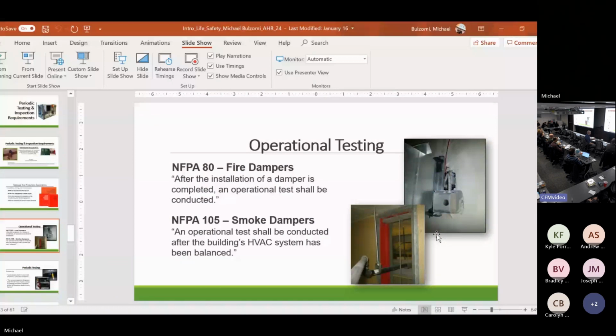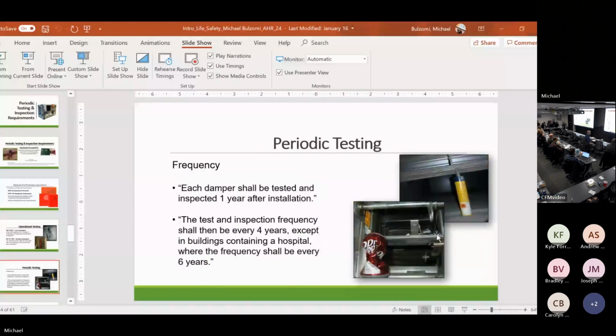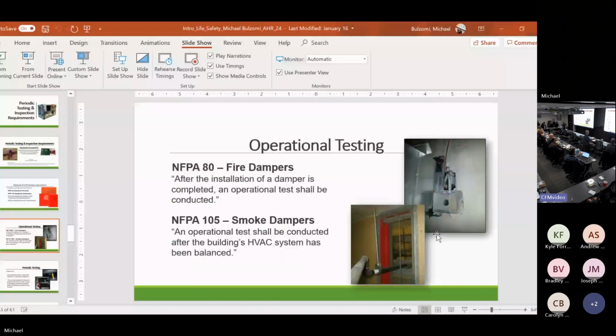So again, we reference the 80 and 105. There's operational testing, and then there's the periodic testing. The operational is the commissioning: I install the damper, the damper works, cool, I'm good. It's conducted after the system's in balance for a smoke damper, or after the installation of the damper is complete for a fire damper.